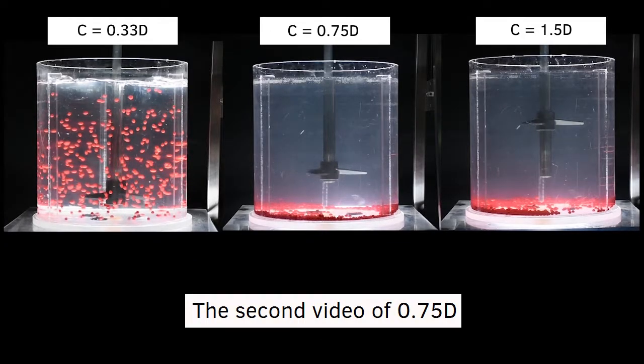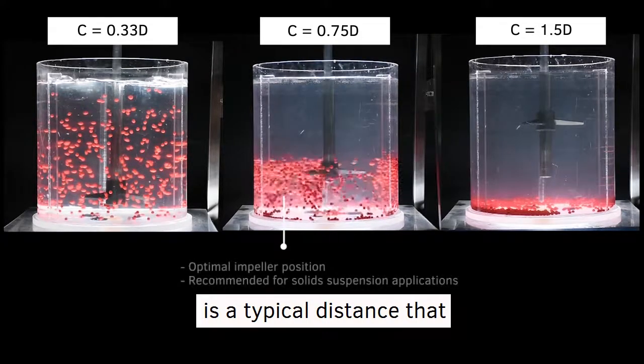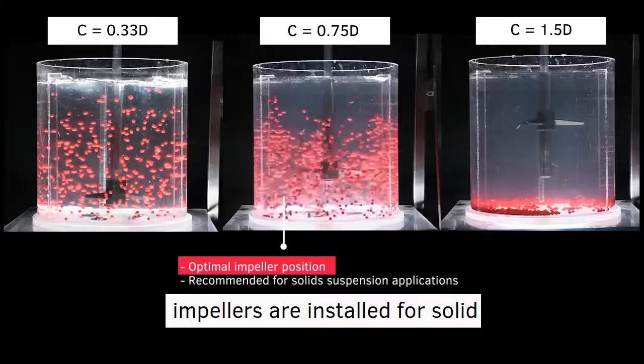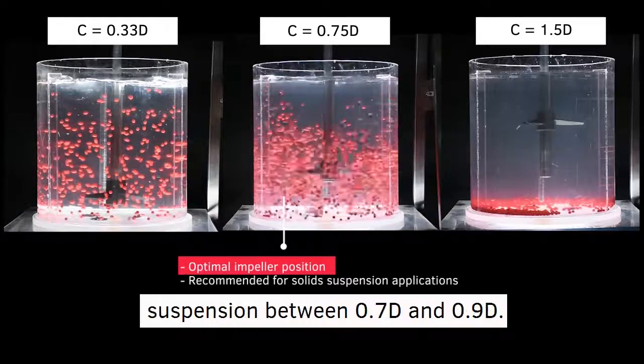The second tank at 0.75D shows the typical distance that impellers are installed for solid suspension, between 0.7 and 0.9D.